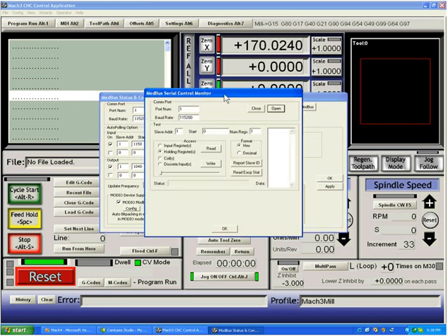By pressing the Test ModBus button, we bring up a special box which is just used to test your ModBus device. You can see here I'm set up for port 1 at 115 kilobaud. Slave address 1. If you have several ModBus devices, they may have different slave addresses. This is how you address them on the port to find which one you're going to talk to. At the current time, you could talk to 4 ModBus devices by changing the slave addresses here to correspond to the various ModBuses.